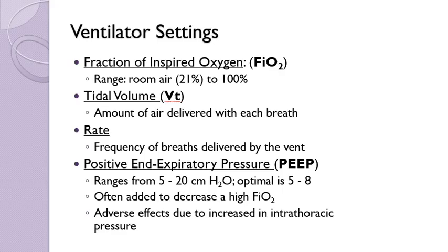And then we have what's called PEEP, positive end expiratory pressure. This is the treatment for ARDS. And what PEEP does is it's extra pressure to keep the alveoli open just a little longer, because when my alveoli are open, I get better gas exchange. So the range of PEEP we can set is from 5 to 20.